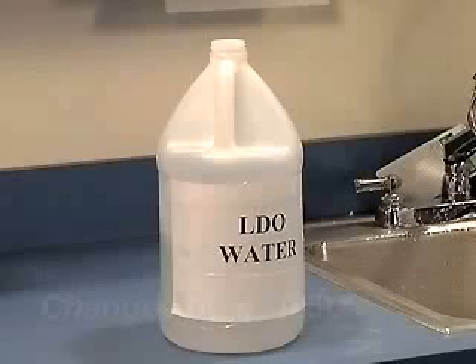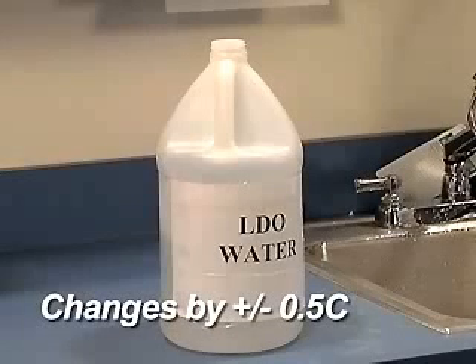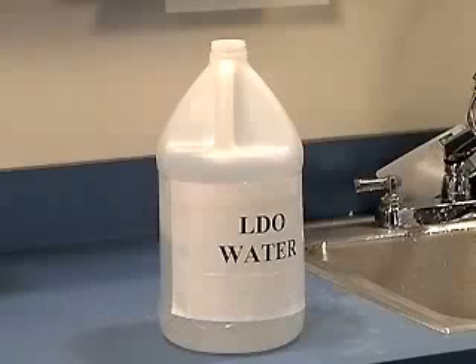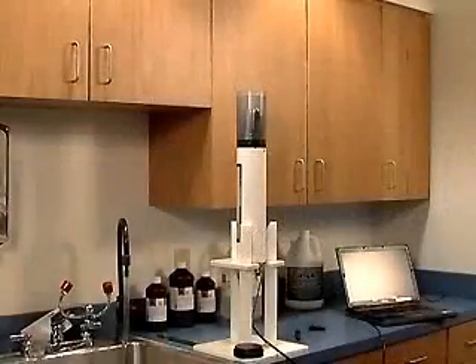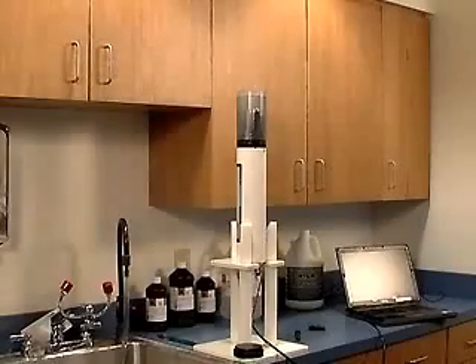If the temperature changes by more than 0.5 centigrade during calibration, dissolved oxygen measurements may be inaccurate and the sensor will need to be recalibrated when the temperature of the water stabilizes. For this reason, the calibration should also not be done in direct sunlight. Stand the sonde so the sensors are pointed upwards with the storage cup attached.